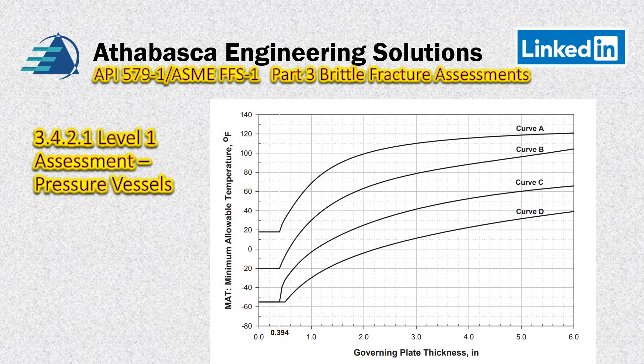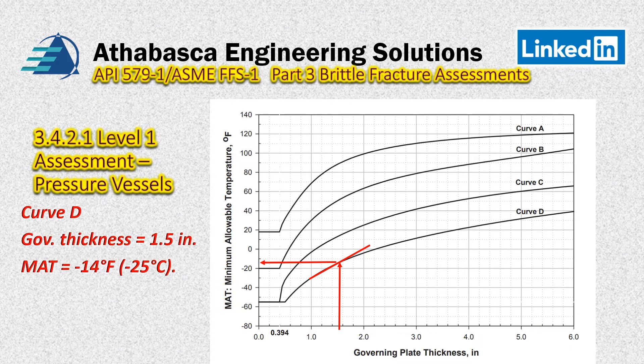Looking at figure 3.4, with our 1.5 inch thickness we go up to Curve D — shown right there — and then we go right across. Our MAT is minus 14 degrees Fahrenheit, or minus 25 degrees Celsius. Curve D, governing thickness 1.5. There are tables also for metric — they call it figure 3.4M for metric.